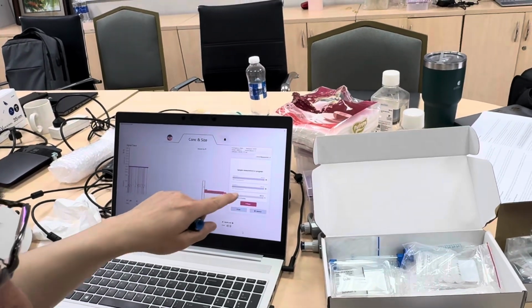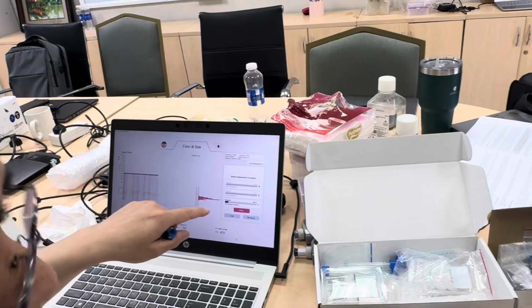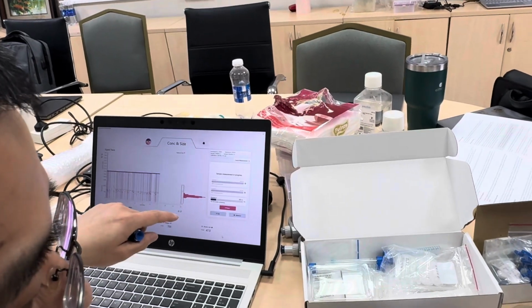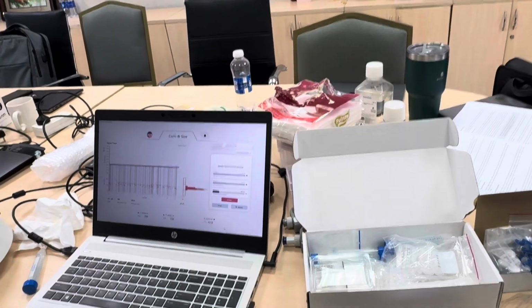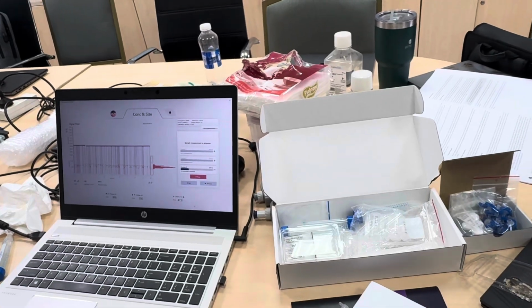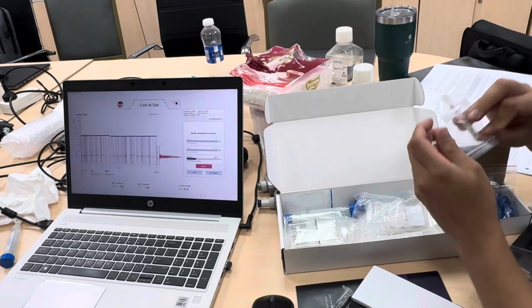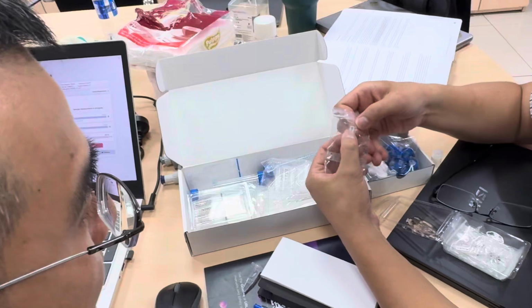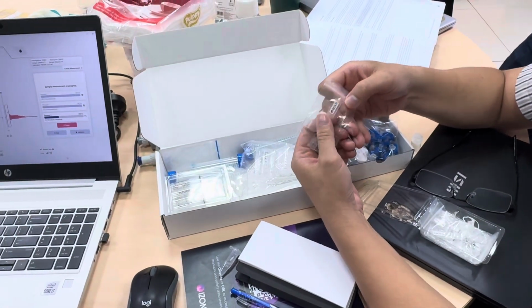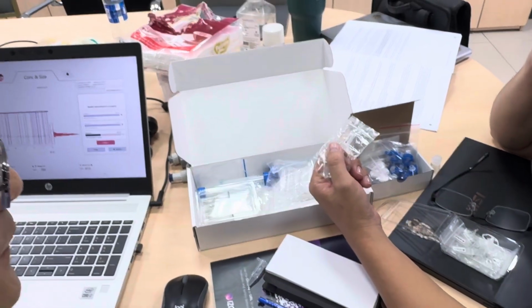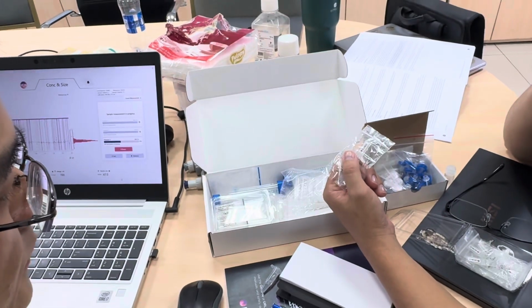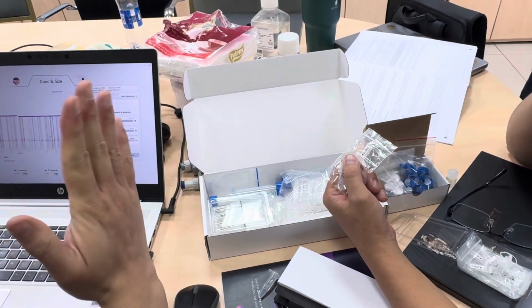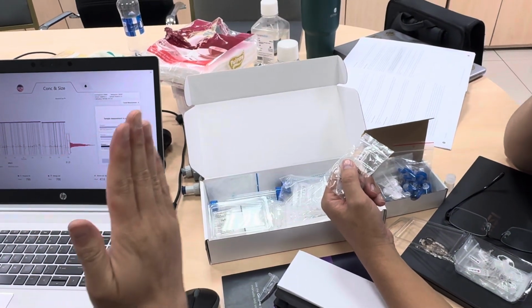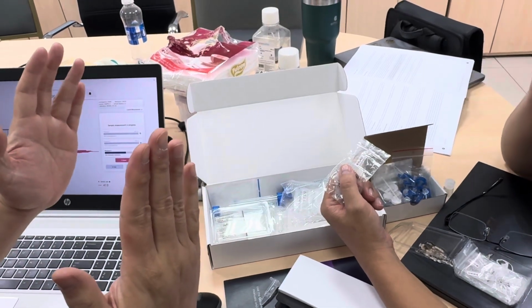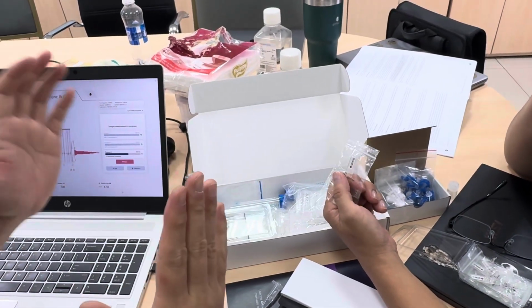You can select which nanopore matches, because when you load the nanopore, you need to input this serial number. Yeah, so it's for our QC purpose. I would like to know this number, 150. That means it's for measuring particles with a mean around 150, which means the lower side maybe around 60 nanometer. So it's the median mean size.